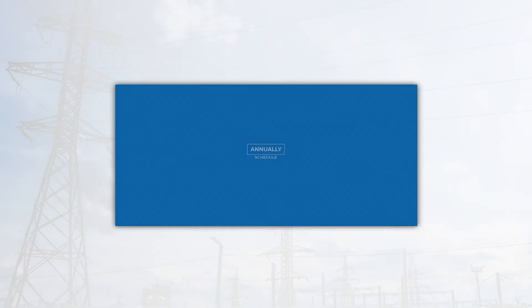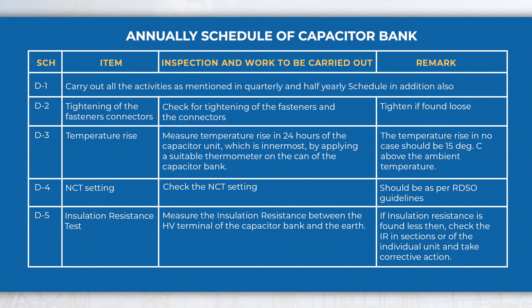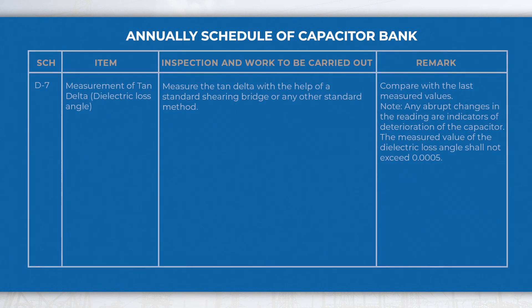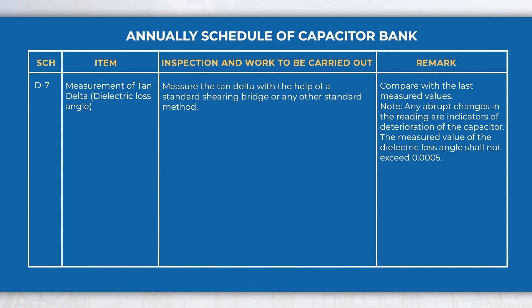In the annual schedule, perform activities like tightening the fasteners and connectors, measuring the insulation resistance and the capacitance value of the individual capacitor units, etc., in addition to half-yearly and quarterly schedule activities.